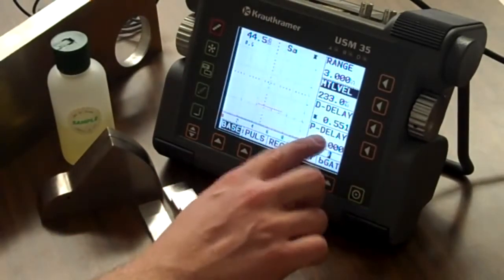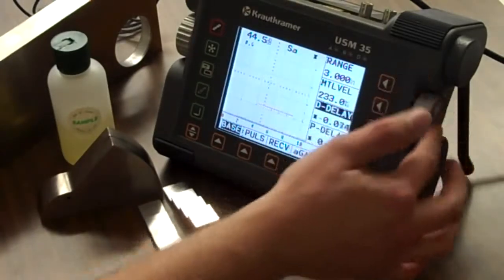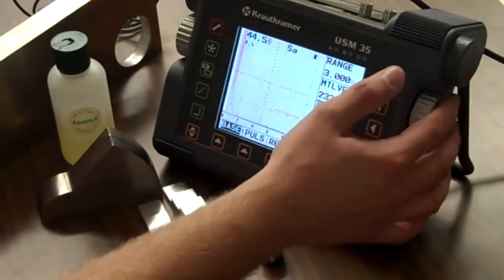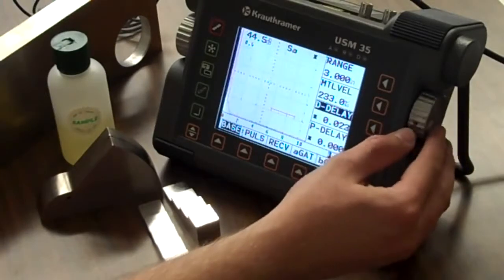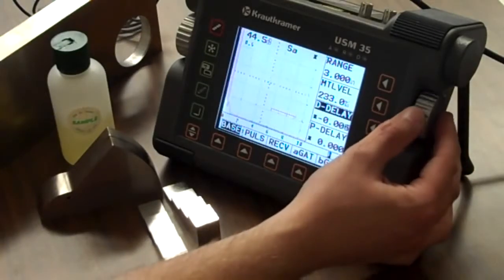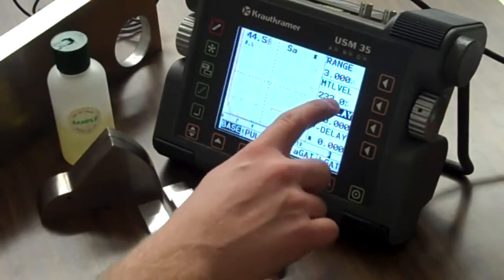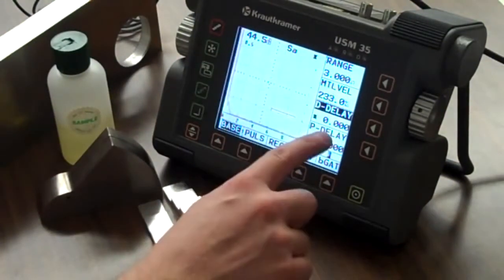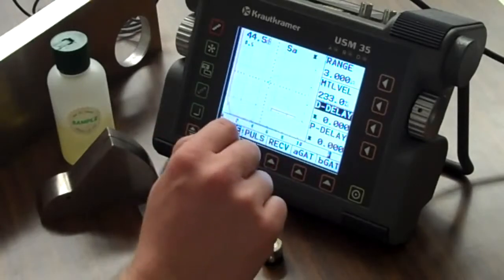Probe delay down here, display delay up here. I'm going to take both of these back to 0. That way that gives us our starting point. So we got a 3-inch range, there's our plain old steel, compressional velocity, display delay, probe delay.